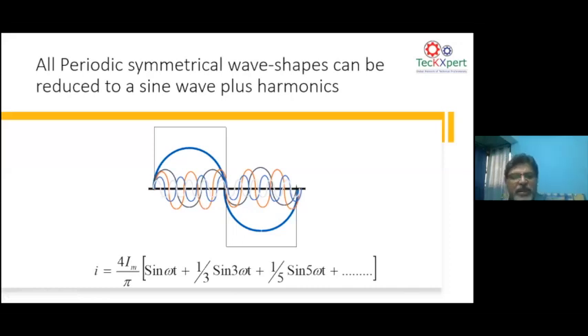Such periodic waveforms are created by full wave rectification. Now, if your rectifier is not a full wave rectifier and it does half wave rectification, then it will have even harmonics along with the odd harmonics. That means full wave rectification will only have odd harmonics. If it is a half wave rectifier, it will have even harmonics also. Now, in normal conditions, if you are using a variable frequency drive and you notice some even harmonics at the input of the drive, that means the drive electronics is not working properly.